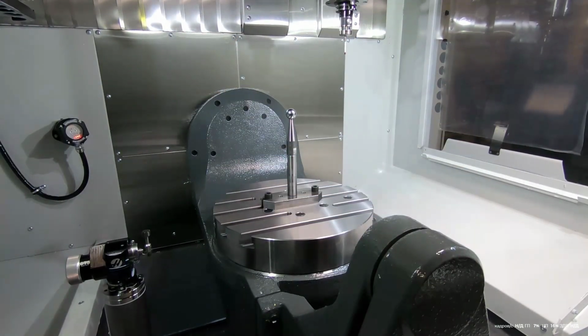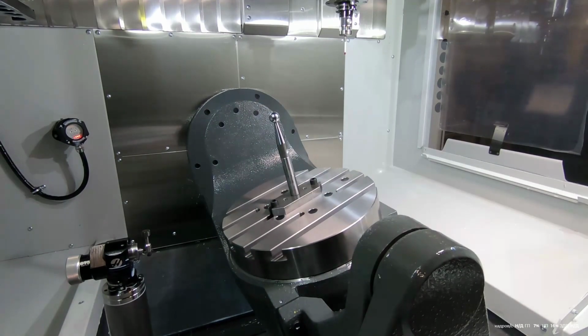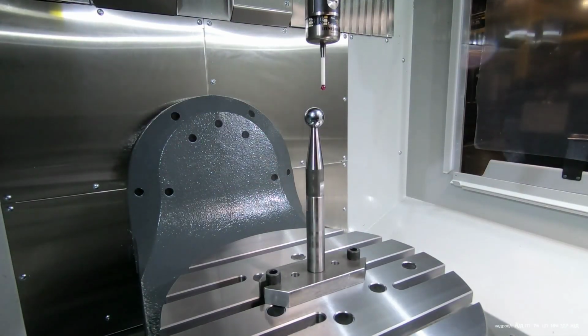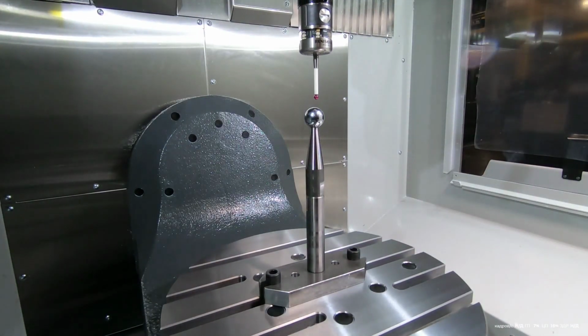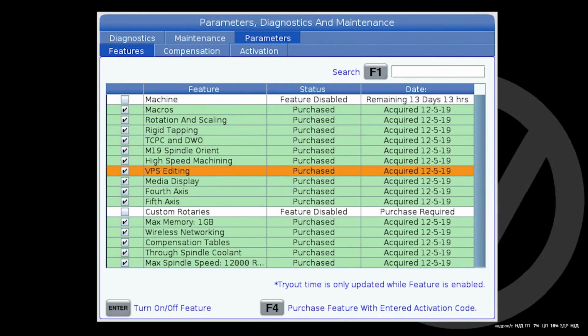Zero return all axes by pressing zero return, then all, and then A. Hand jog the probe so that the probe tip is 100 thou above center of the calibration sphere. Check to see if VPS editing is enabled by pressing Diagnostic and navigate to Parameters, then to Features. If it is not enabled, contact your local HFO.